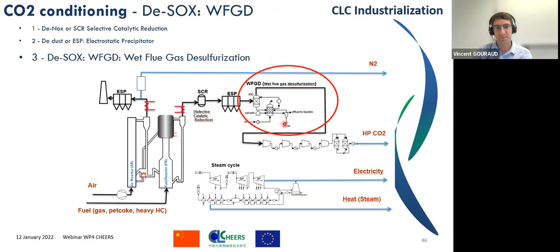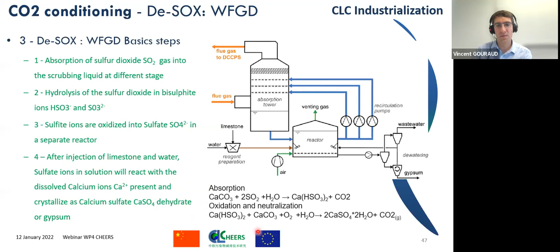The last one is the flue gas desulfurization to remove the SOx. For this technology, we use a 2-step desulfurization unit with an absorbing tower, letting a scrubbing liquid go through the sulfur dioxide, then bringing this liquid into a reactor tank where you do oxidation and neutralization of the sulfite, transforming it into gypsum.